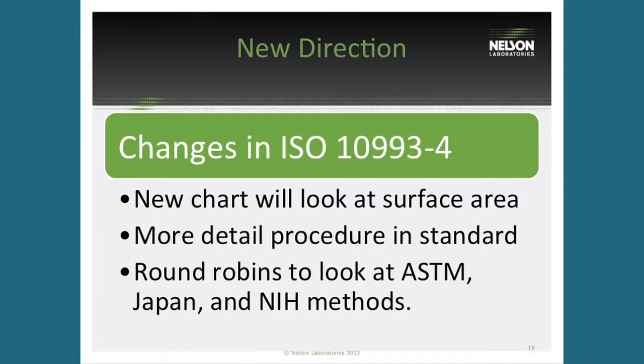So what changes are we looking at in ISO 10993-4? The first change — and probably the most useful for you — is that we're writing a new chart to help evaluate what tests to run for your devices. I'm actually on the subcommittee for this chart. This chart will be based on surface area. The first decision tree will be: does your device have a large or small surface area? The discussion right now is what determines a large versus small surface area, and once we determine that criteria we'll have better discussions on what testing has to be run.